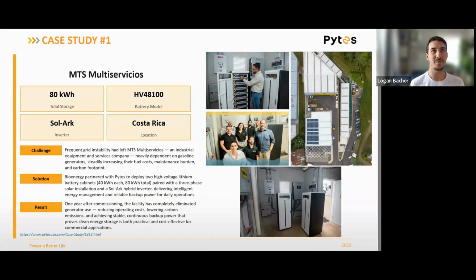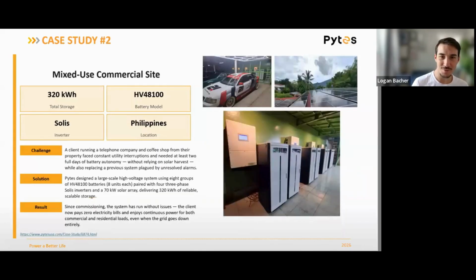That was sort of a generic answer on how the batteries interact with the inverter. More specifically, looking at an example like this - and I had this up for a minute, so I'll use this as a chance to show a different case study - these are Solis inverters, but notice I've said this multiple times: 1 to 1, 2 to 1. In this case, which is actually in the Philippines, we've got two cabinets for every inverter - 2 to 1, 2 to 1, 2 to 1, 2 to 1.